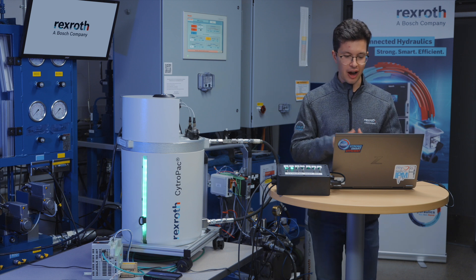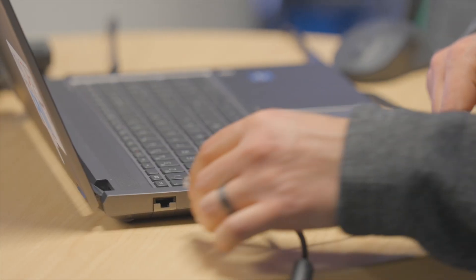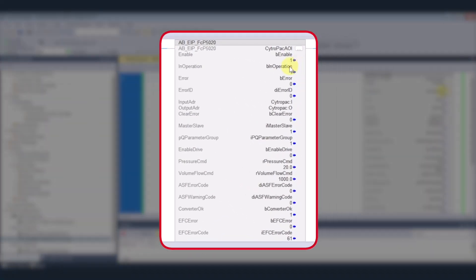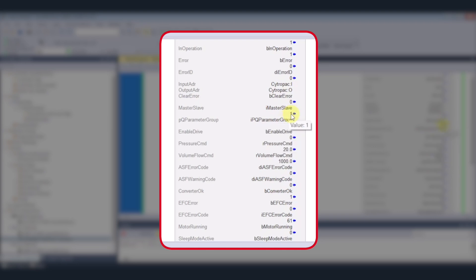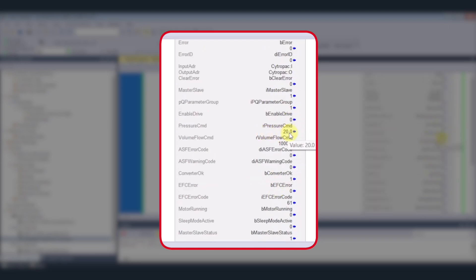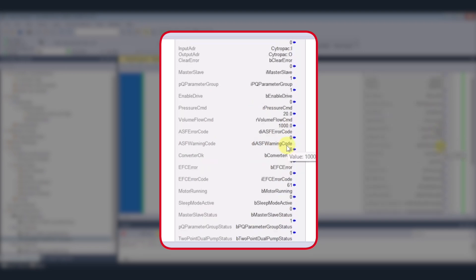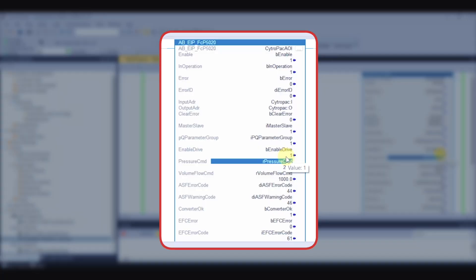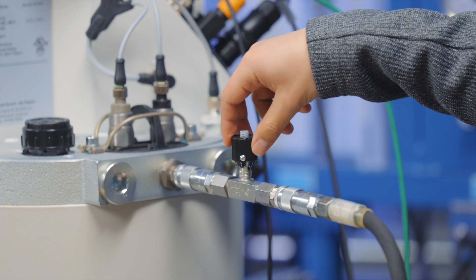Before we go online, we need to make sure that we are actually connected via multi-ethernet, so I have to connect my Ethernet cable. Now we're online and we're in run. I have the AOI imported into the main routine. To actually use the AOI, you need to have it enabled, master/slave set to one, parameter group set to one. In this case, I'm going to do the same pressure command of 20 bar and volume flow of 1000 RPM as in the previous part. Once I enable the drive, it will start up the CytroPac as before, but now we have direct command of it via your PLC. You can also change the speed or change the pressure for whatever part of the cycle you need, and it will react the same way as with the fixed pressure and fixed flow command.